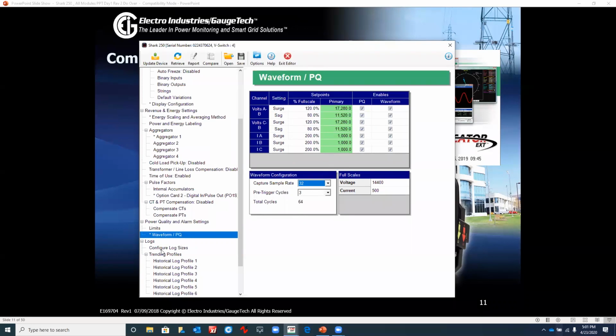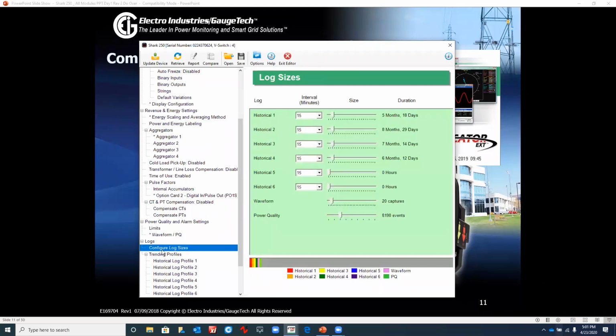So let's go to the logs, historical logs. First, we talk about the log sizes. This meter has 6 historical logs where you can set up the parameters from the finest resolution at 1-minute intervals to 60-minute intervals. And here are your sliders. You can specify how large you want those logs to be. Depending on how much data, let's say if you only program historical log 1, you probably want to extend that to a larger size. If you don't want as much data on, let's say, historical log 6, you would set it to 0.